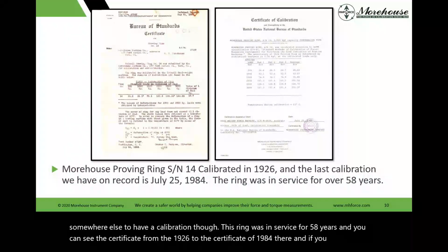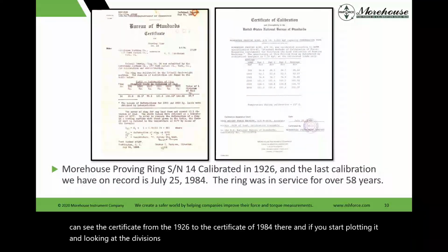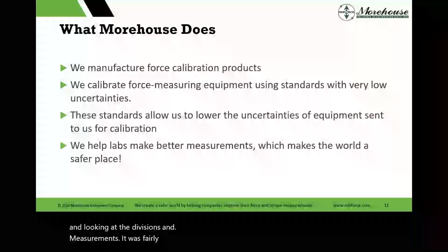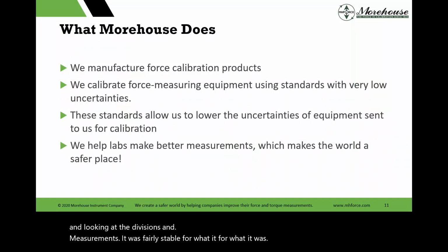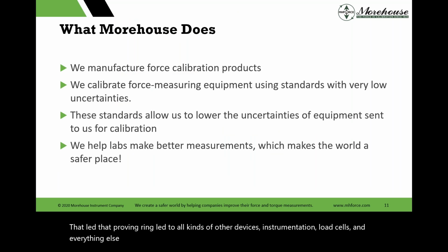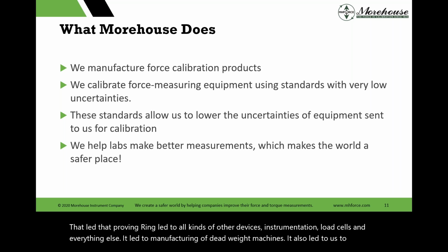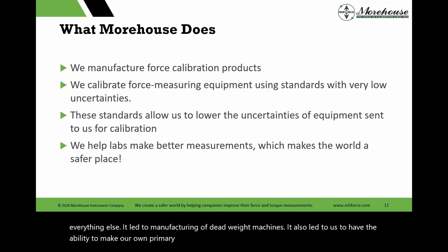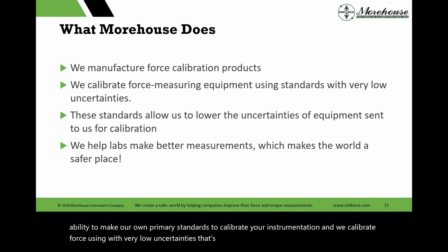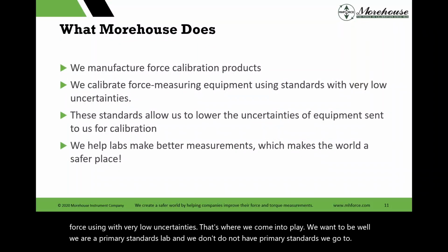And if you start plotting it and looking at the divisions and measurements, it was fairly stable for what it was. That proving ring led to all kinds of other devices, instrumentation, load cells, and everything else. It led to manufacturing of dead weight machines. It also gave us the ability to make our own primary standards to calibrate your instrumentation, and we calibrate force with very low uncertainties. That's where we come into play. We are a primary standards lab, and when we do not have primary standards, we go directly to NIST for our secondary standard comparisons, our load cells.